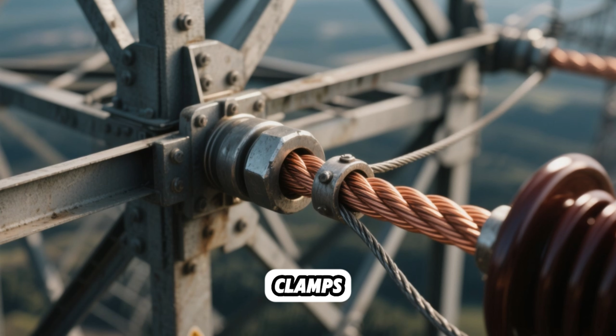These aren't just simple clamps. They're heavy-duty cables that essentially short-circuit the line to the steel tower, ensuring that any stray or induced voltage has a safe path to ground.